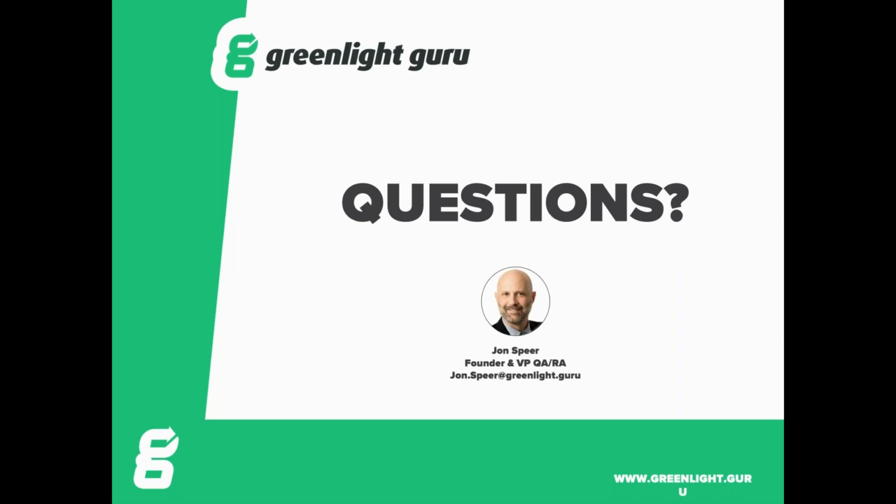Yes, okay, so if I understand what Dan's saying, intended use is important, and trying to identify what that is sooner rather than later, and more or less sticking to that throughout the process, will be to your benefit. If you keep changing your indication for use and your intended use of your product, you'll have to go back and revisit your user needs and your design inputs over and over and over again. So really good point that Dan makes.